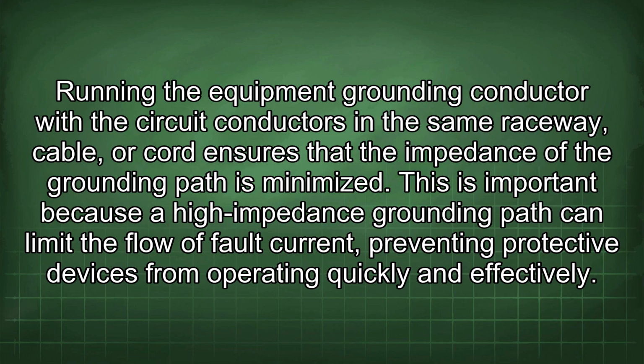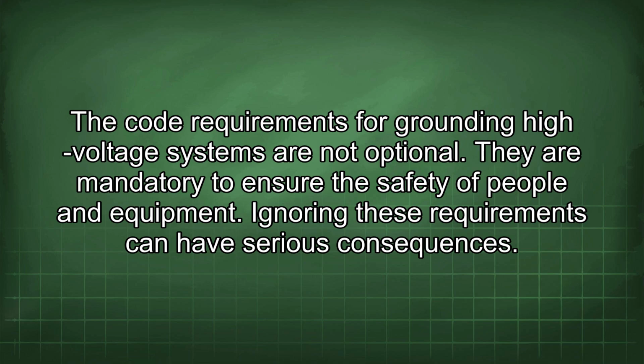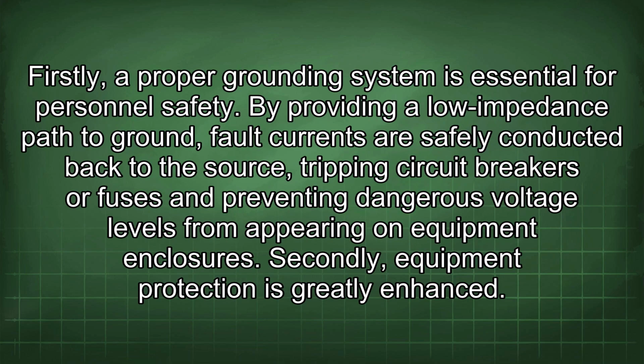The code requirements for grounding high voltage systems are not optional. They are mandatory to ensure the safety of people and equipment. Ignoring these requirements can have serious consequences. Firstly, a proper grounding system is essential for personnel safety. By providing a low impedance path to ground, fault currents are safely conducted back to the source, tripping circuit breakers or fuses and preventing dangerous voltage levels from appearing on equipment enclosures.